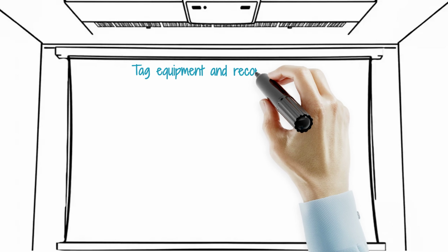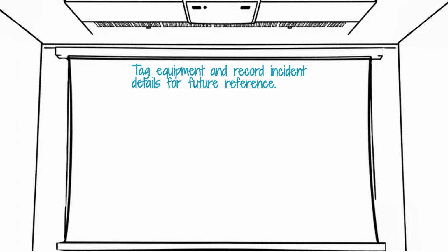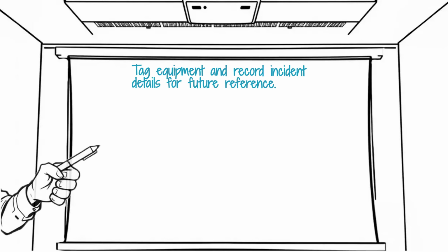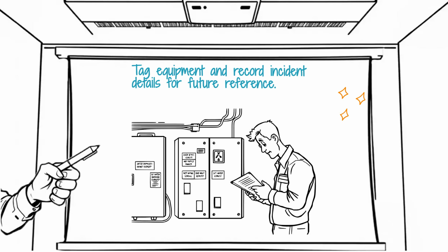Segregate the damaged equipment. The condition should be clearly tagged: water damaged, do not energize. Record the incident details, including the depth of the water, the time of ingress, and the nature of the equipment affected.